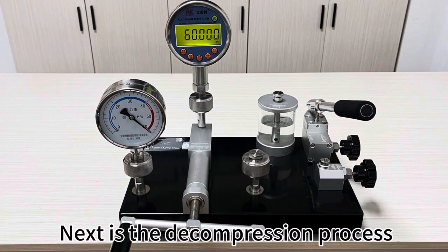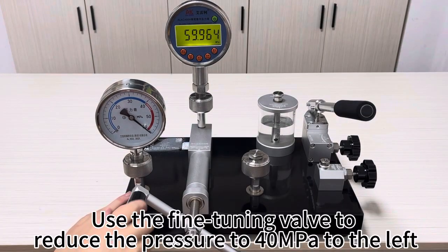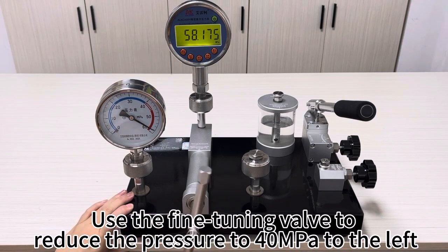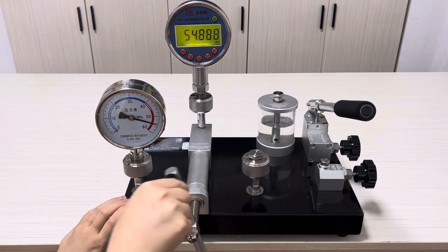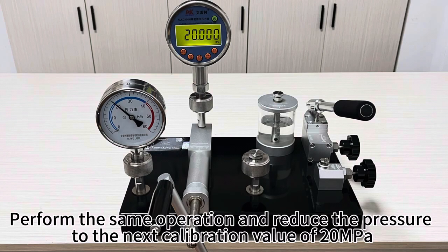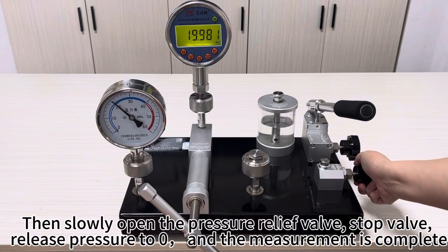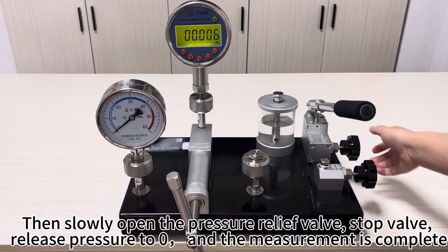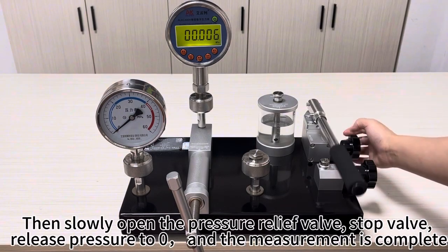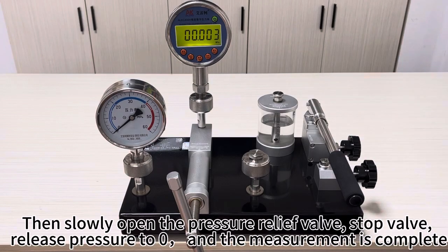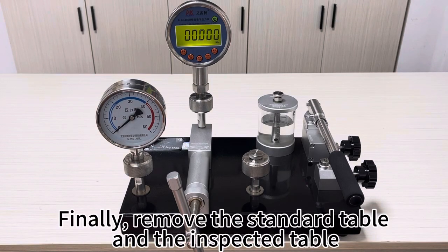Next is the decompression process. Use the fine-tuning valve to reduce the pressure to 40 MPa to the left. Perform the same operation and reduce the pressure to the next calibration value of 20 MPa. Then slowly open the pressure relief valve and stop valve, release pressure to 0, and the measurement is complete. Finally, remove the standard table and the inspected table.